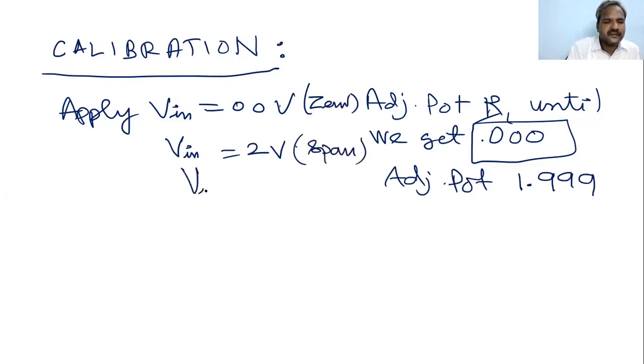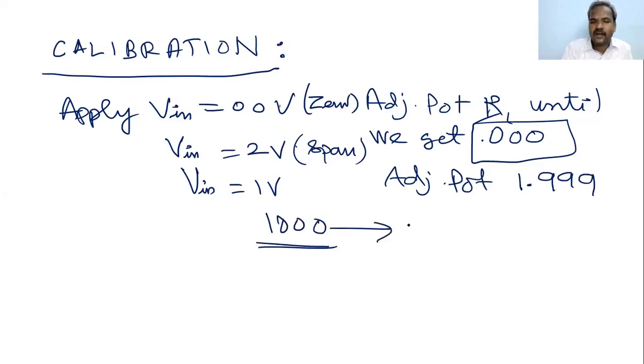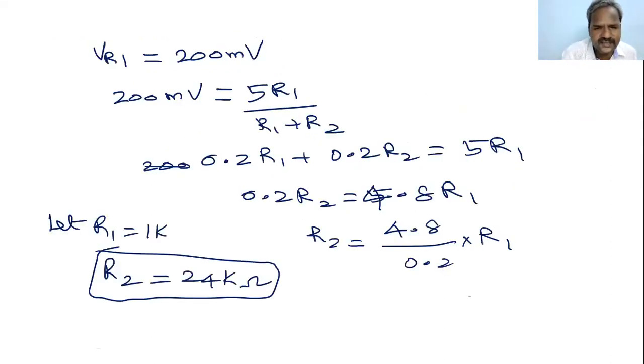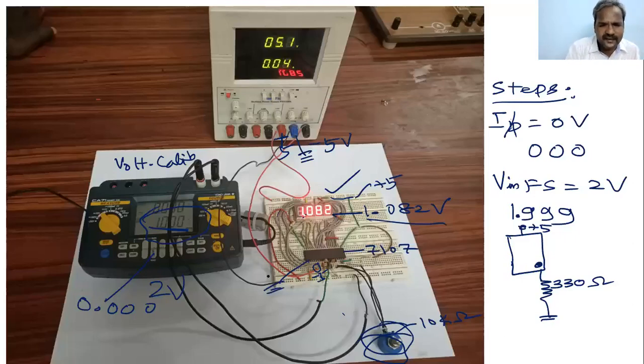Next, the linearity check. Vin equal to 1 volt, the middle value. Check the display. The display should give 1000. All of these are counts. If we make a decimal in the display here, it reads as 1.00 volt. Understand that now? This is the calibration procedure for the 2 volt full scale range. Similarly, we have to do the design for 200 millivolt full scale.